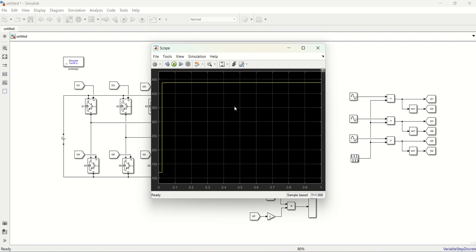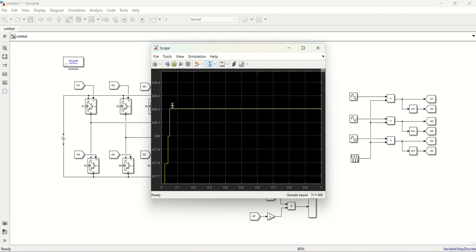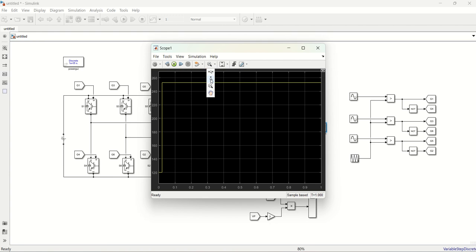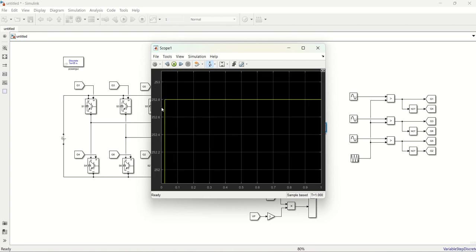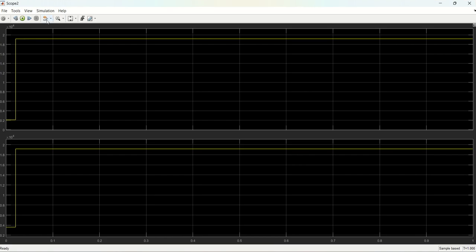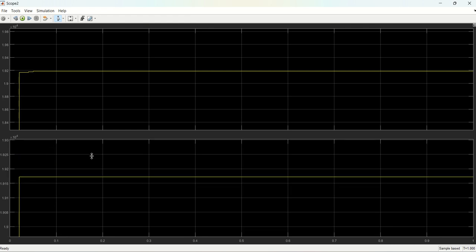Now we'll check the line voltage. We have calculated it, we try to check this result. It is coming around 438. Okay, 438. This is the phase voltage, it is coming around 252. Now you can check here, so the power is the same. Power is 1.92.